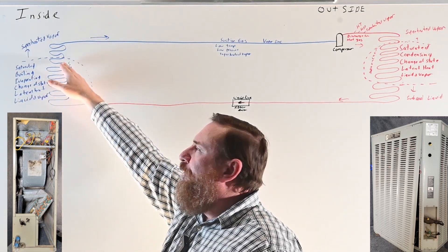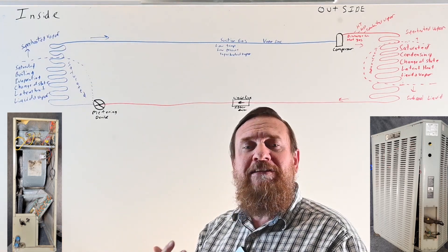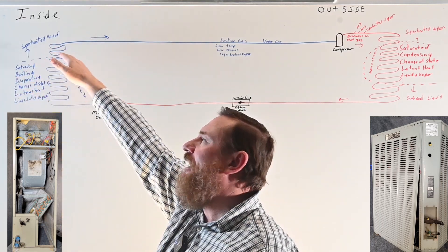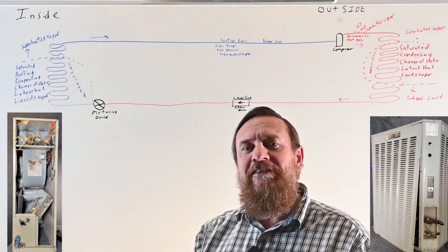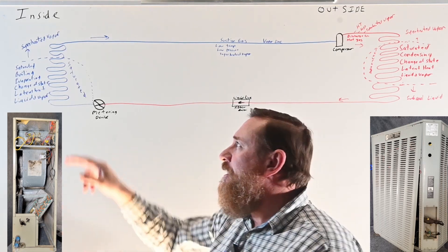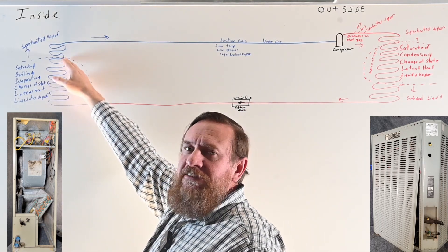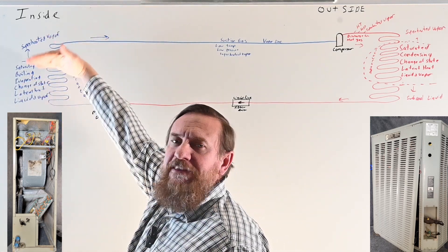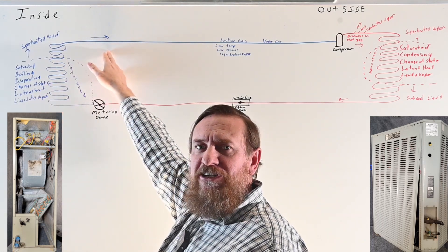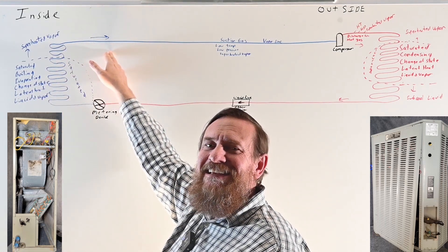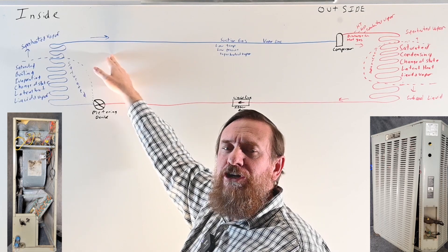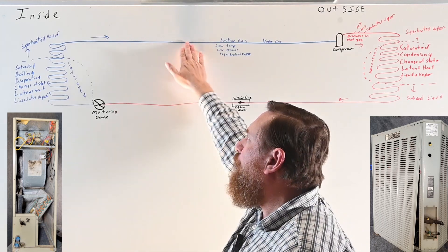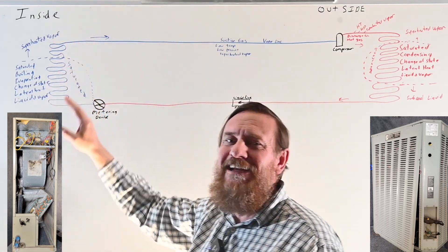After all the refrigerant boils from liquid to vapor through most of the evaporator coil, it's still only 40 degrees. We can still absorb heat — the 75-degree air goes to that 40-degree vapor. The difference is now the vapor starts superheating, sensible heat, rising from 41, 42, 43 degrees and so on, superheating above the saturation point. So in the suction gas line, we have a low temperature, low pressure, superheated vapor — it feels cool to you but it is superheated above its saturation point.